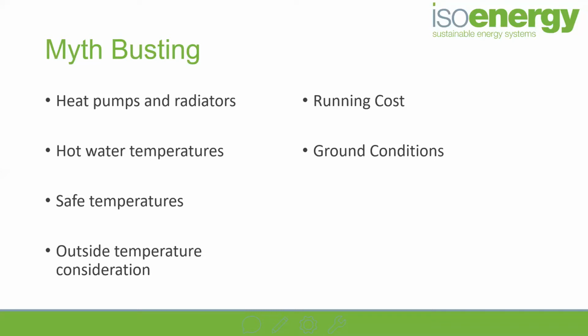When we put in that third borehole, and we replumbed the system as well to make it more efficient because the hot water never got up to temperature, the running cost dropped down to £1,200 a year. It was so high because the boreholes had actually frozen. So the brine temperature coming into the heat pump was -9. The heat pump was cutting out because that temperature is too cold for it to provide a safe running operation, and so it was calling in its electrical inline heater as a backup.